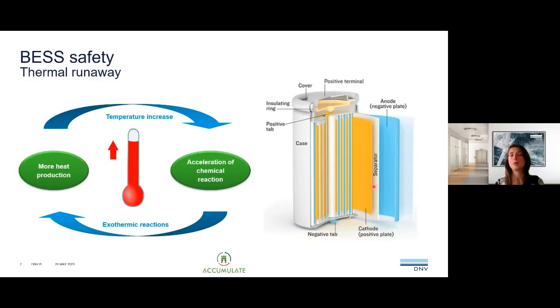This is also why, for this kind of fire propagation test, when a part of the system where the batteries are is above 80 or 85 degrees Celsius, you should not use your battery again. You should consider it lost because it's damaged.